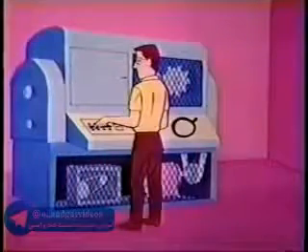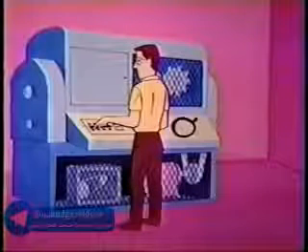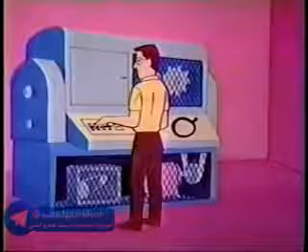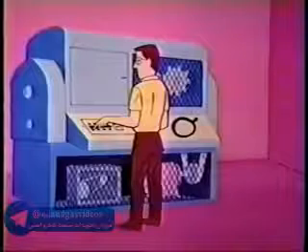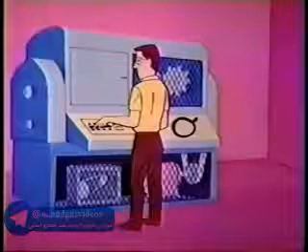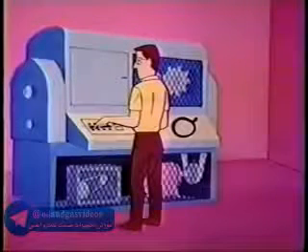The present code requirements identify certain conditions that do not come under the lockout-tagout program. These conditions are normal production operations unless personnel exposure exists as a result of the removal or bypass of a guard, or having any part of an employee's body in the point of operation of a machine, or any associated danger during a machine cycle.